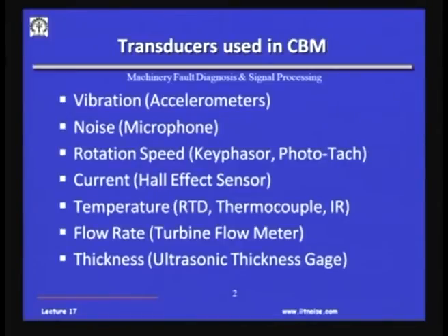But the turbine flow meter is another device which could be very easily put online on a pipeline, and then all you get is the speed at which the fluid is flowing through it. Once you know the area of the pipeline, if you multiply that, you will get the flow rate instantaneously. So, when the processes are very dynamic, when the flow rates are changing because of the operations on the plant, particularly in large oil refineries and chemical plants, that is where we use turbine flow meters.